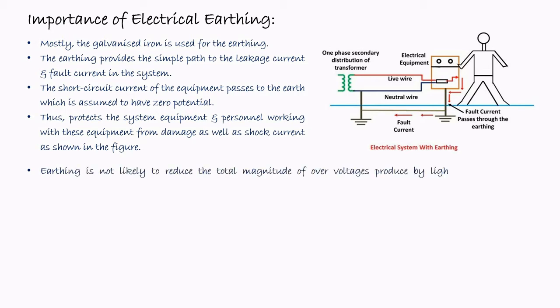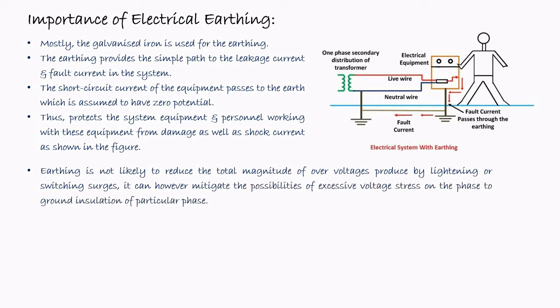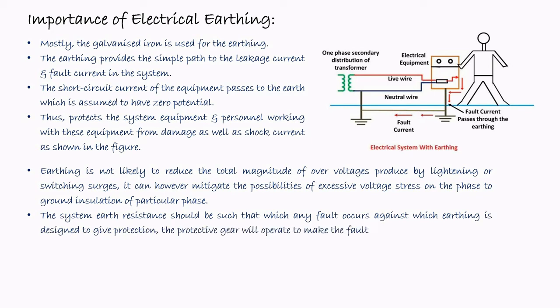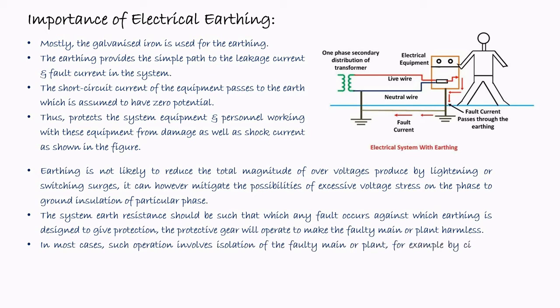The earthing is not likely to reduce the total magnitude of the overvoltage produced by lightning or switching surges. It can, however, mitigate the possibility of excessive voltage stress on the phase to ground insulation of a particular phase. The system earth resistance should be such that, whenever any fault occurs against which the earthing is designed to give protection, the protective gear will operate to make the faulty main or the plant harmless. In most cases, such operation involves the isolation of the faulty part, for example by the circuit breaker or the fuses. Normally, the earth leakage circuit breaker or ELCB is used for this purpose.